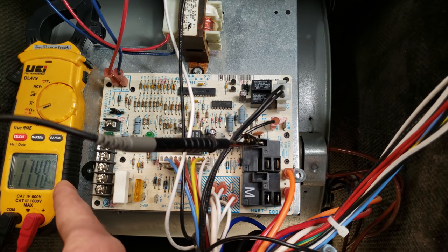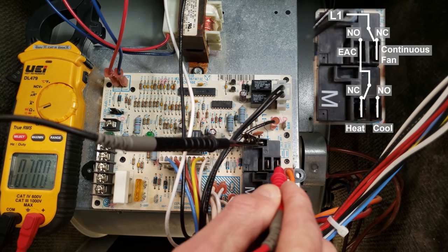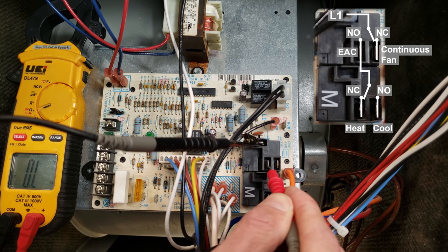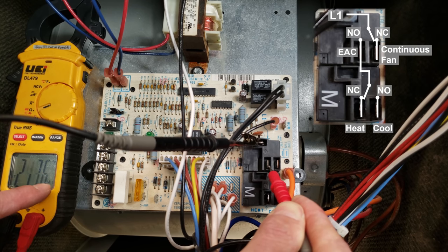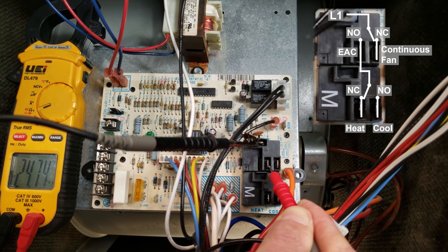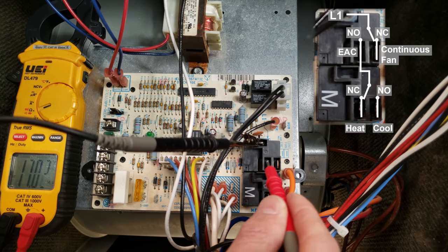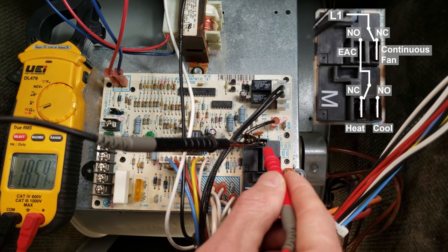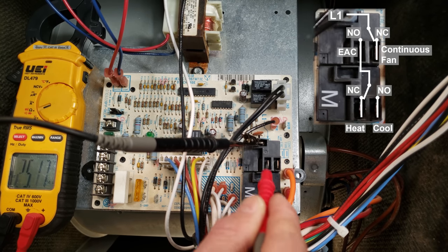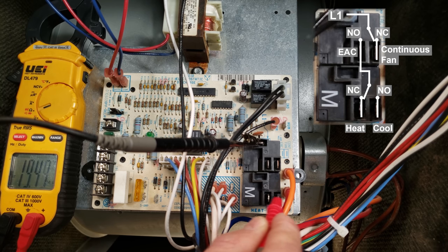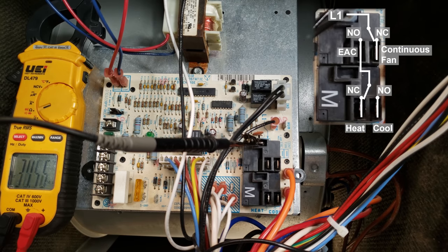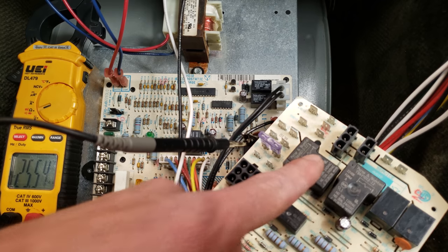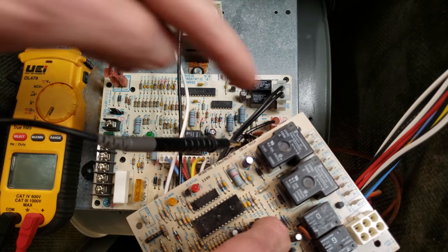Now I have the power off to the furnace and I've switched my multimeter over to resistance. What you're going to do is you can test from here to the continuous fan, you should have 0.0 ohms of resistance, and over to the EAC it should not be connected. You see it's actually in mega ohms so that is not connected. If it is connected or if it has anywhere say 5 ohms or 10 ohms or something like that, you'll know that there's some burnt contacts in there, it's kind of stuck in position. So you should have nothing between here and down here, mega ohms, and that's because the power is going to need to travel through here over to one of these two.